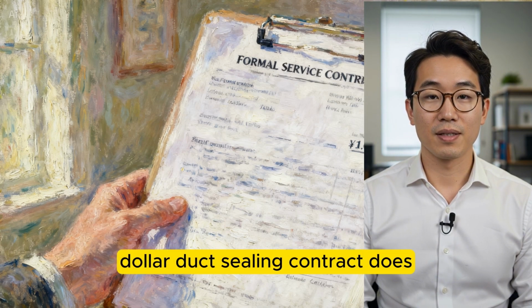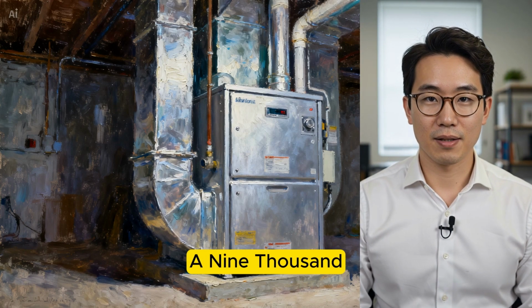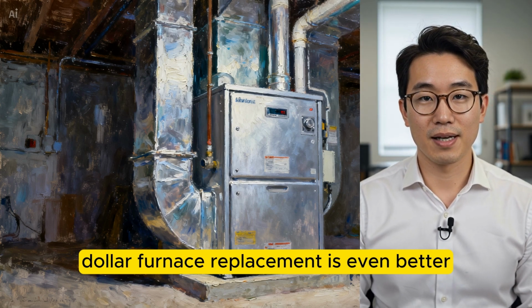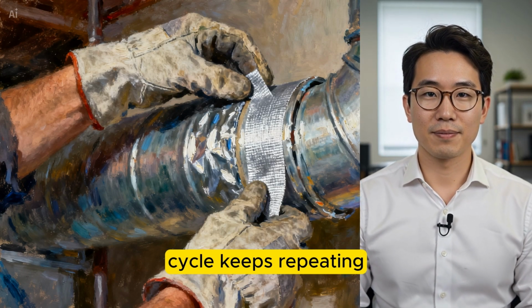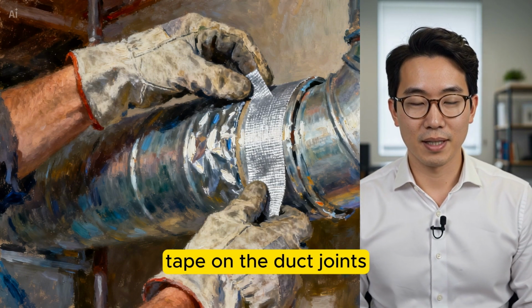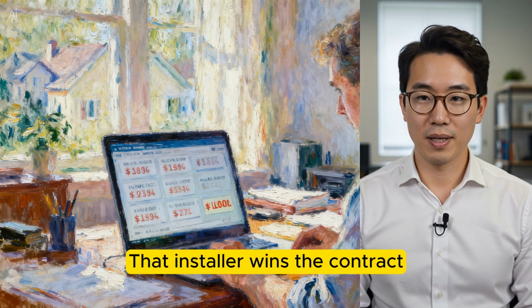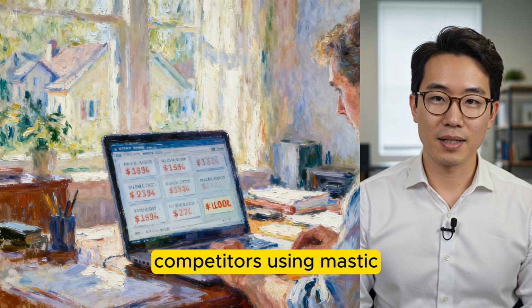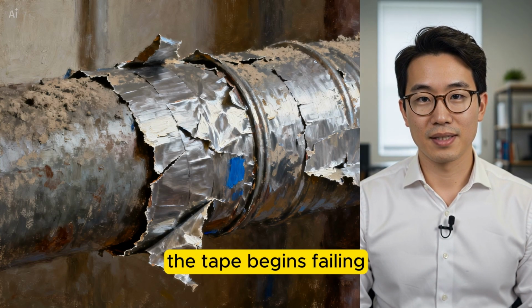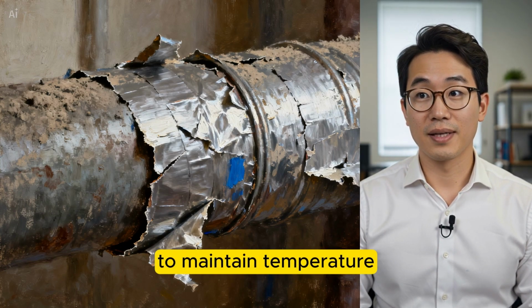A $3,000 duct sealing contract does. A $9,000 furnace replacement is even better. And this is how the cycle keeps repeating. An installer uses cloth-backed tape on the duct joints. That installer wins the contract because the bid comes in cheaper than competitors using mastic. 2 years later, the tape begins failing. The house struggles to maintain temperature.